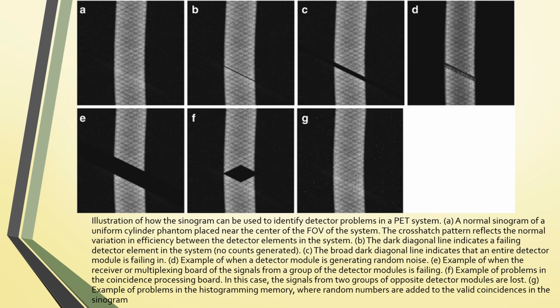With F, that's an example of problems in the coincidence processing board. In this case, the signals from two groups of opposite detector modules are lost. And then with G, that's problems with the histogramming memory, where random numbers are added to the valid coincidences in the sinogram.